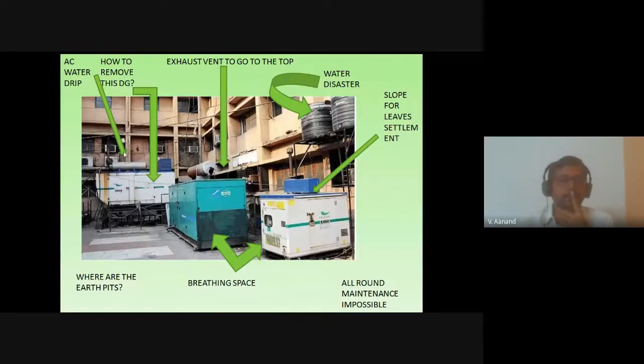See, you have already mentioned these things - there is an AC water drip from the split AC units. I can't remove this DG. The exhaust vent has to go to the top. This is a water disaster waiting to happen - note the slope for leaves settlement and breathing space.